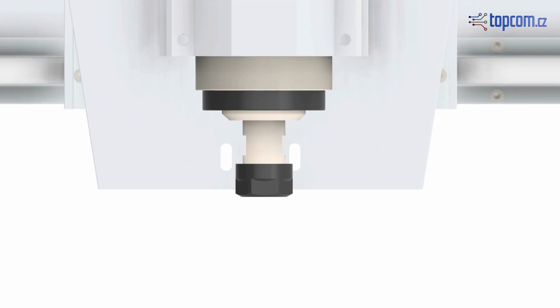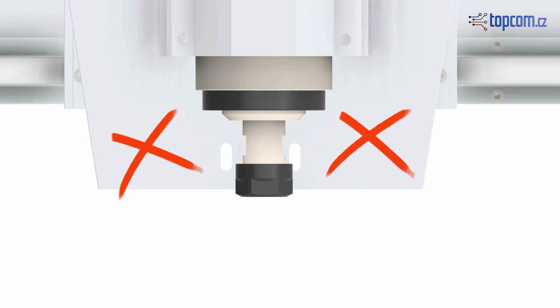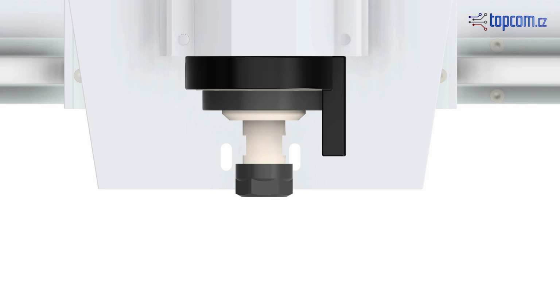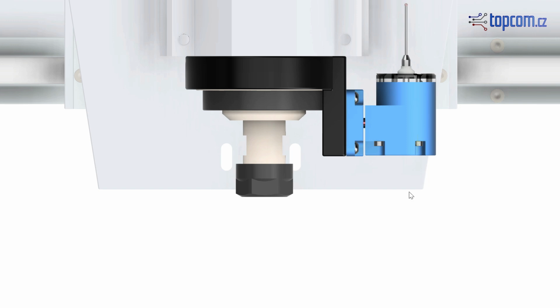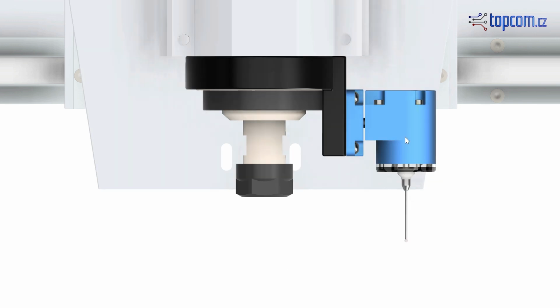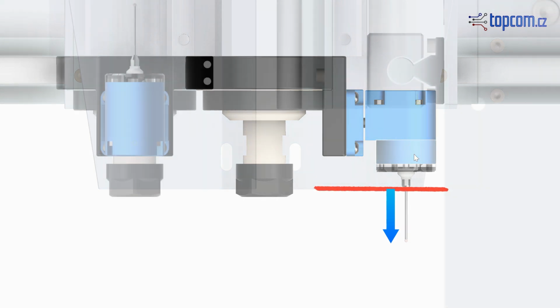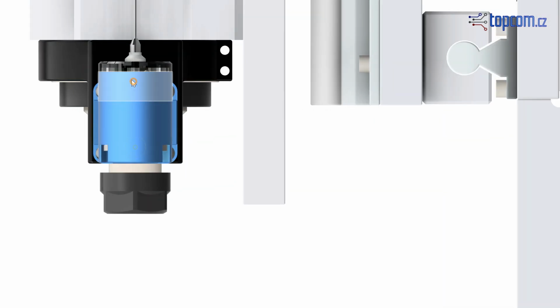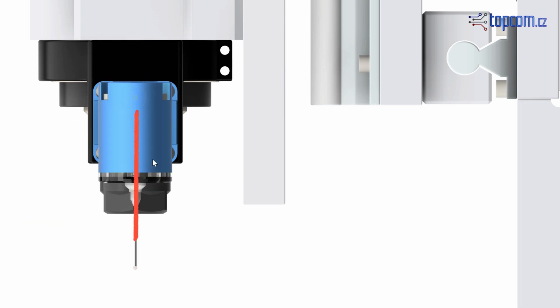If there isn't enough space on the Z-axis body to mount the rotary probe, an alternative is to attach the probe to the spindle. For this, a spindle mounting clamp can be used. The probe is then mounted to the clamp. The height alignment in this setup is similar to direct mounting on the Z-axis. In the home position, the probe must not extend below the lowest surface of the Z-axis, but it should get as close as possible. This allows full use of the stylus length when the probe is in the working position. The clamp is designed to position the probe approximately in line with the spindle axis.